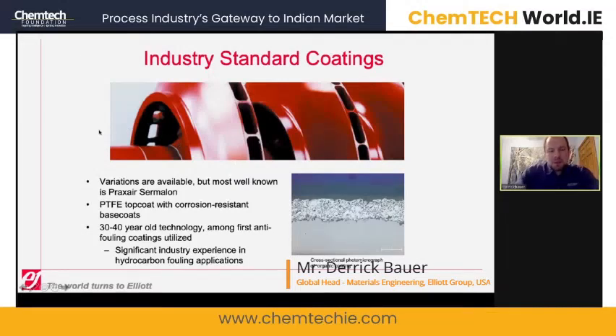Within the centrifugal compressor industry, one of the most standard or commonly available coatings, I call it an industry standard just because that is really what it has evolved into, is really just a non-stick coating. It has a corrosion resistant undercoat. It's basically a ceramic undercoat, and then the top coat is really just a PTFE, or commonly referred to as a Teflon top coat. Really no different than the Teflon top coats that are on cookware.